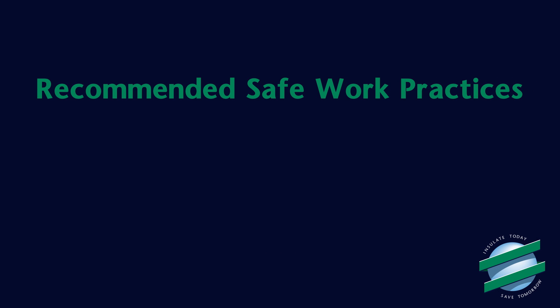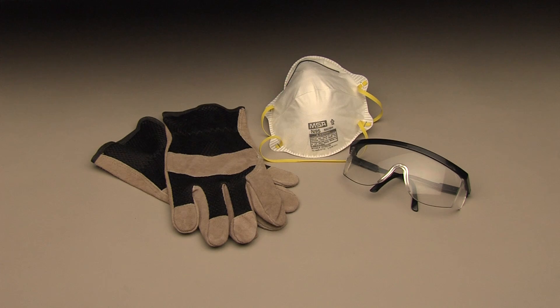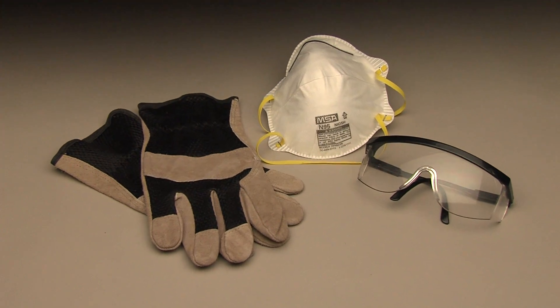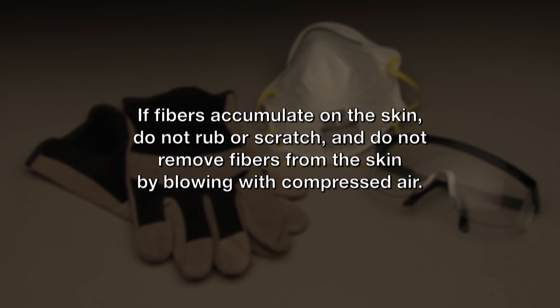There are some recommended safe work practices that are important to know when working with fiberglass duct board systems. For comfort, NAIMA recommends the use of protective equipment such as loose-fitting, long-sleeved, and long-leg clothing and safety glasses when handling, fabricating, and installing fiberglass insulation products. To minimize upper respiratory irritation, a NIOSH N95 2-strap respirator can be worn for comfort. If fibers accumulate on the skin, do not rub or scratch, and do not remove fibers from the skin by blowing with compressed air.